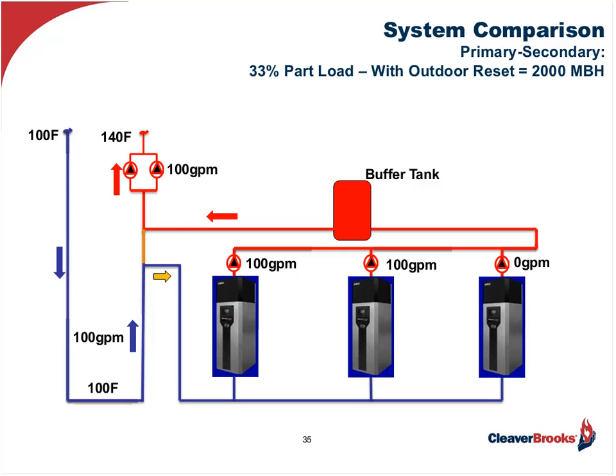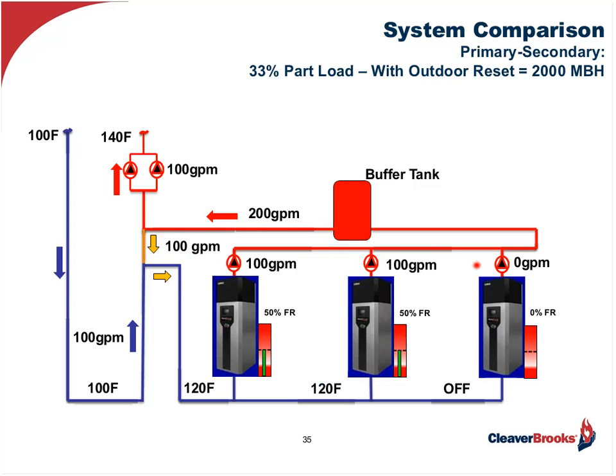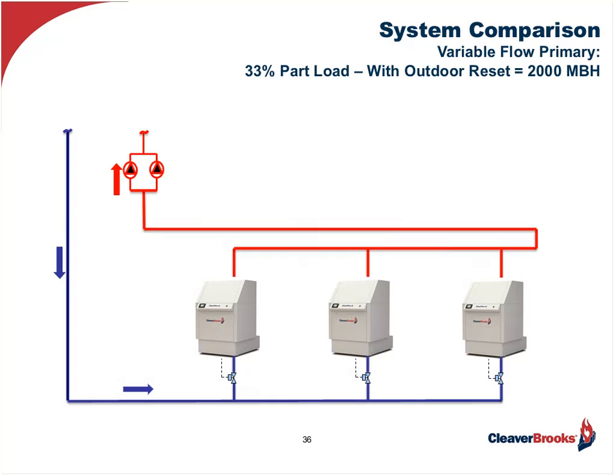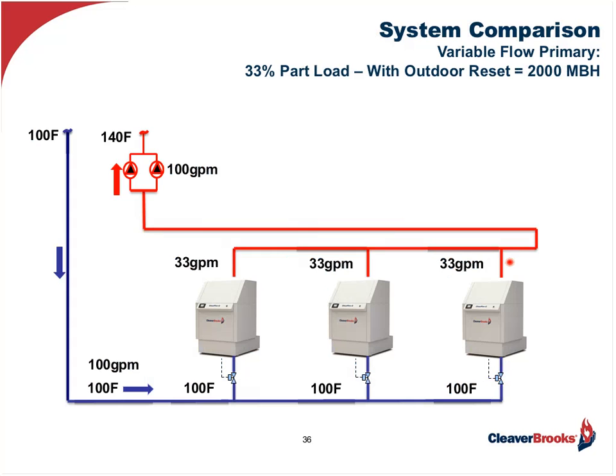Staging of the boilers is much less critical with variable flow pumping. We're going to have 200 GPM in the primary loop with 100 GPM coming back, and that gives us 120. So we've just raised the return water temperature to the boilers by 20 degrees. And the 2 boilers will be operating at a 50% firing rate. Looking at variable flow primary, again, the system stays the same, but we run all 3 boilers, and we have the true 100-degree Fahrenheit water coming back to the boilers, and because we're running 3 of them, we're at a 33% firing rate.